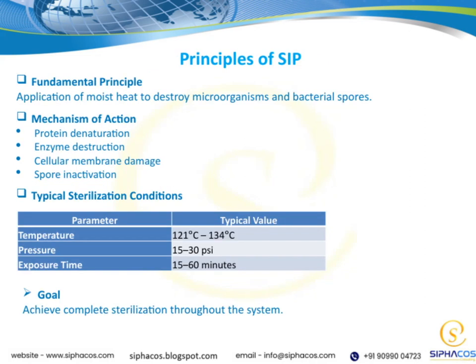Our goal here is clear: to achieve complete sterilization throughout the system. We rely on specific conditions: temperatures between 121 and 134 degrees Celsius, pressures from 15 to 30 psi, and exposure times lasting 15 to 60 minutes. The key principle is using moist heat to destroy all microorganisms and bacterial spores. This works by denaturing proteins, destroying enzymes, damaging cellular membranes, and inactivating spores. These combined effects ensure thorough sterilization every time.